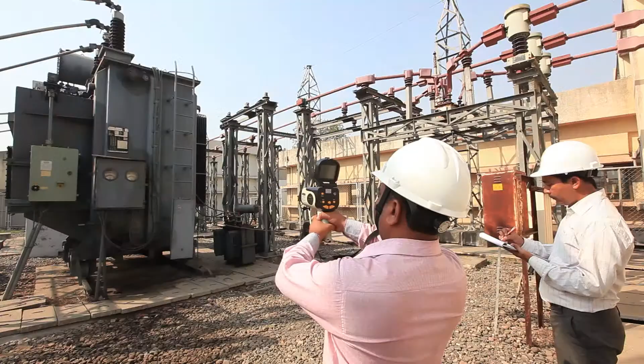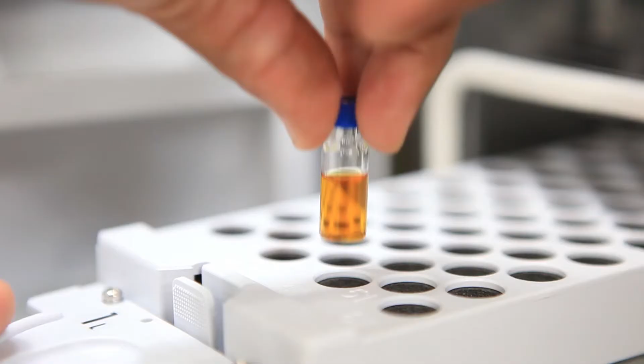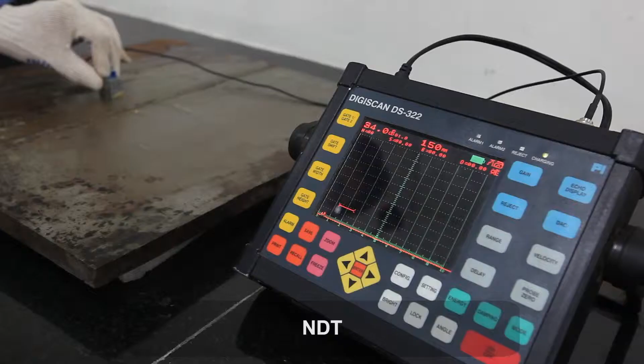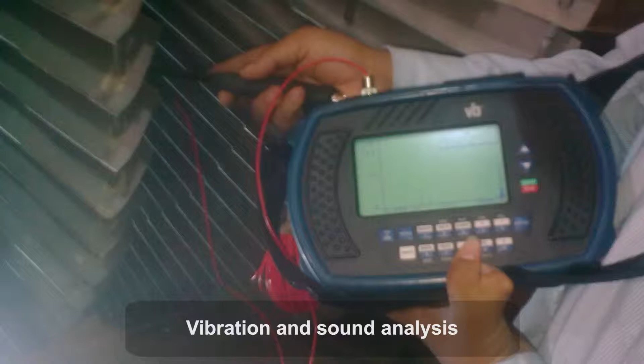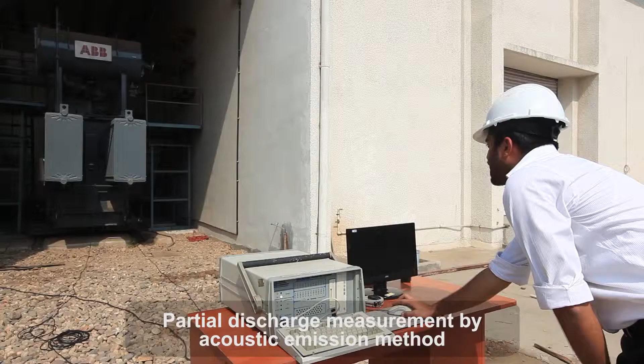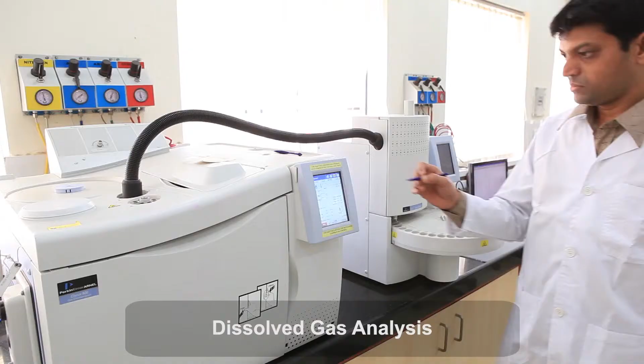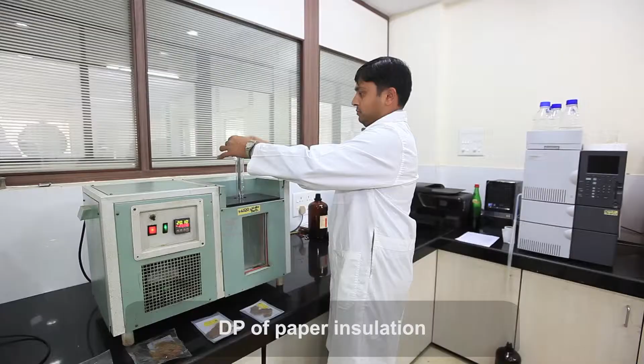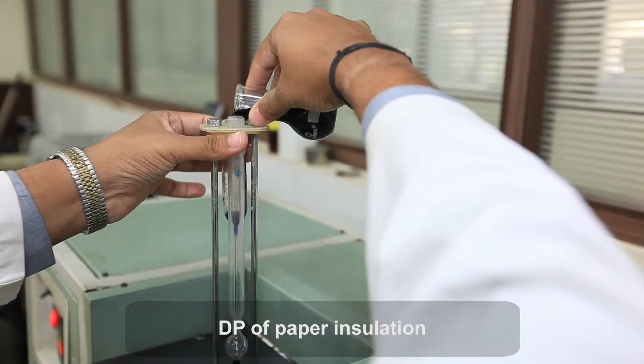Research and development in the area of diagnostics is important to correctly predict failures and remaining life of power equipment. The major techniques employed are in-situ metallography, NDT, vibration and sound analysis, partial discharge measurement by the acoustic emission method, motor current signature analysis, sweep frequency response analysis, dissolved gas analysis, furan analysis, and DP of paper insulation.